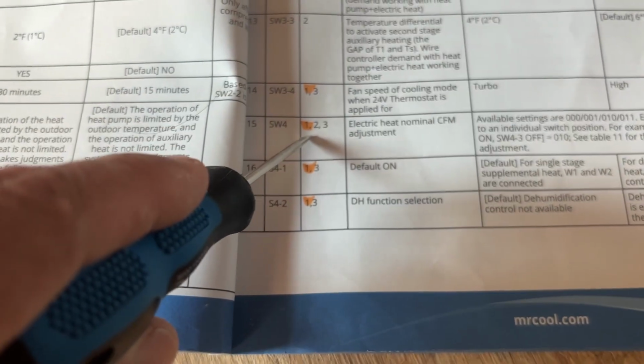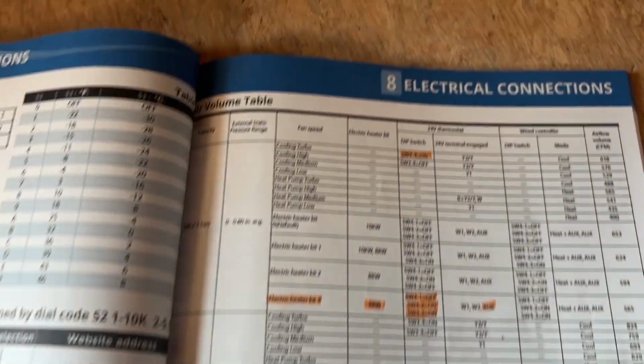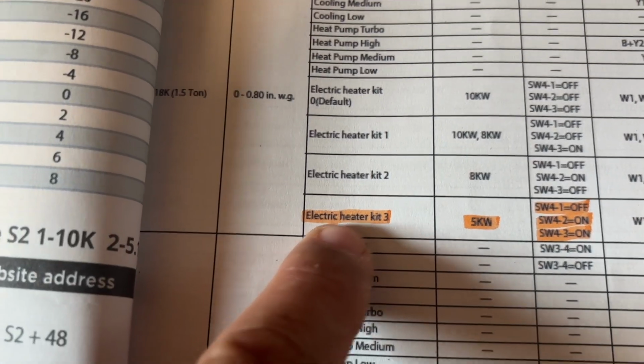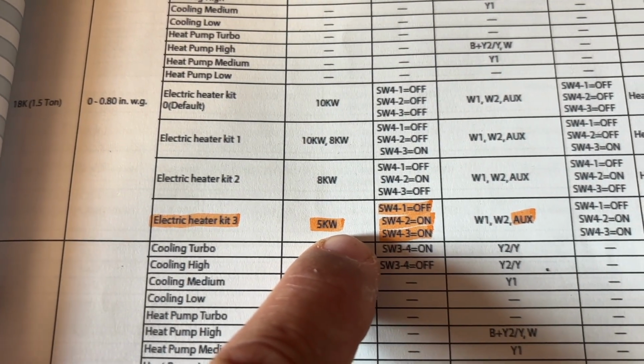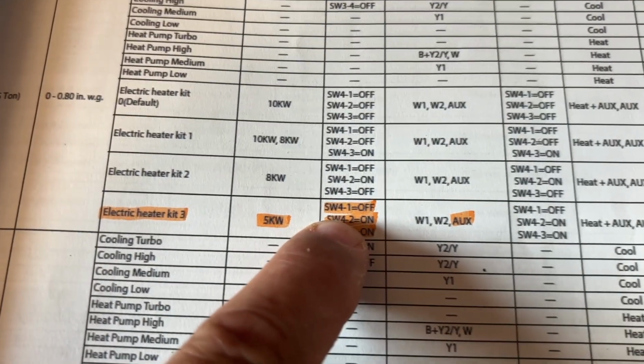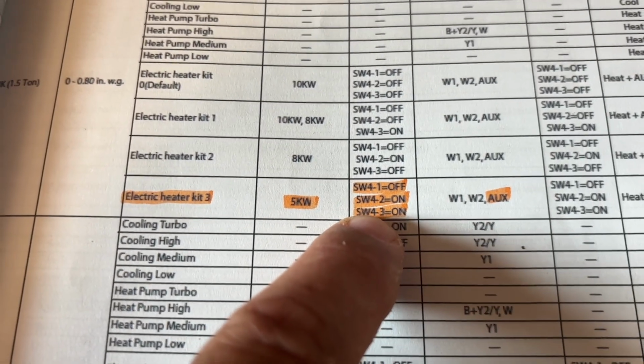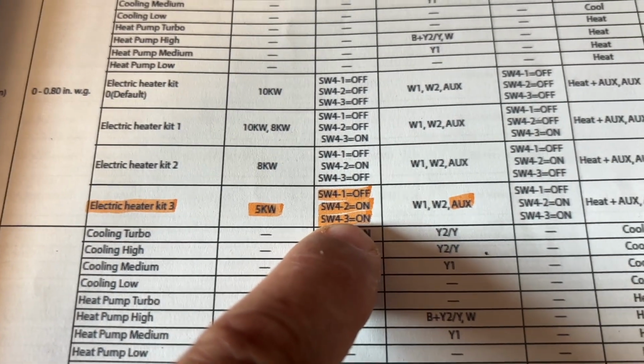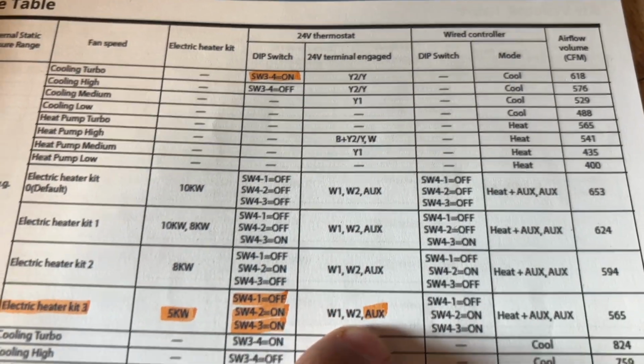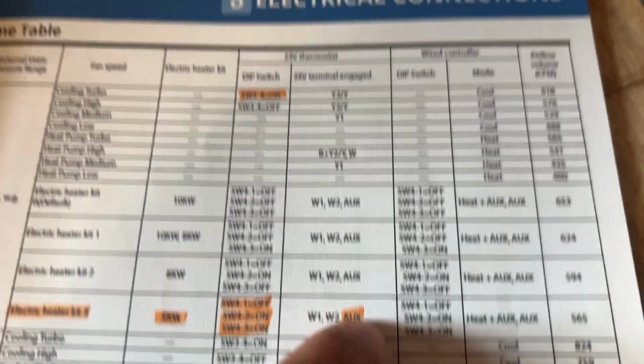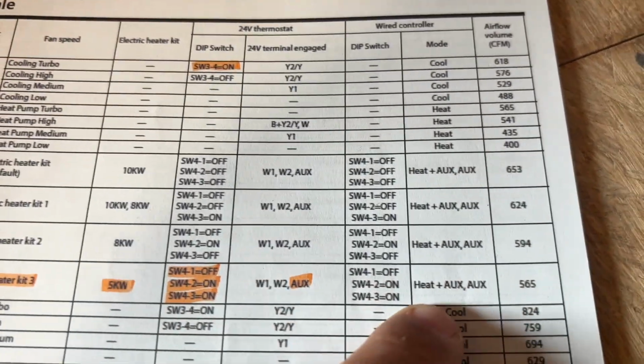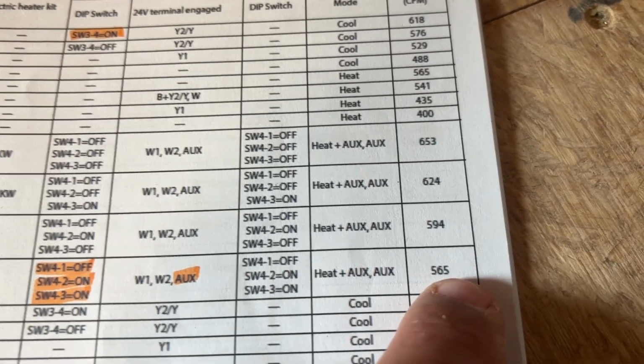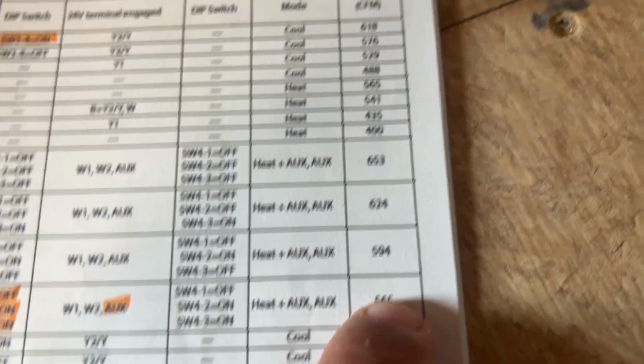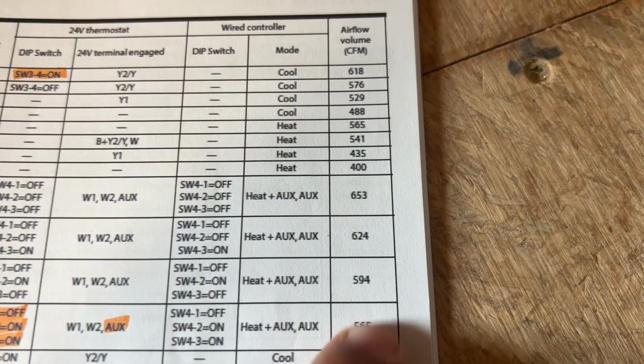So let's come back down here and look at this. SW4, control scenario 1, electric heat, CFM adjustment. So for me, we're gonna go back to this table. Electric heat kit 3 is what I have, the 5 kilowatt. So SW41 set to off, SW4, 2, and 3 set to on. It's going to use the W1, 2, and AUX terminals, which we have the AUX hooked up, and that's going to put my blower at 565 CFM.